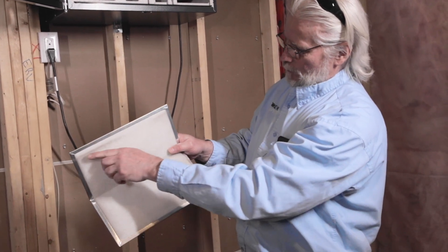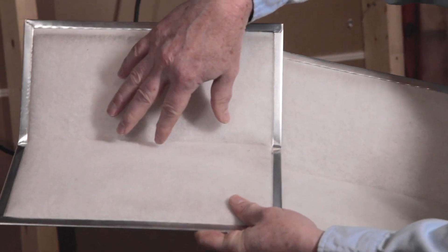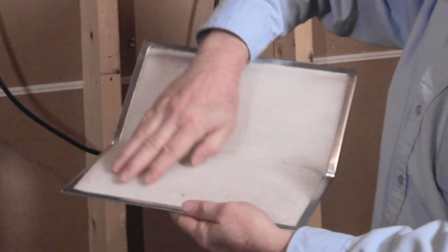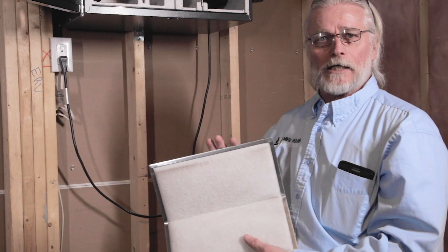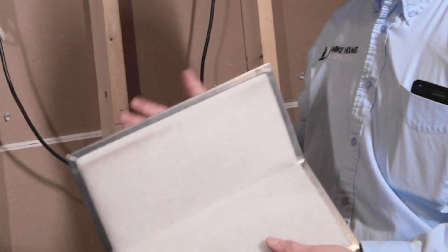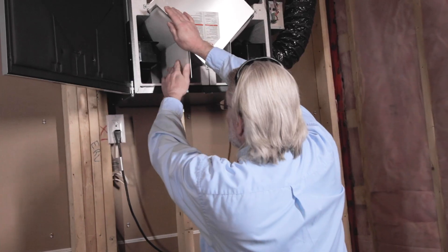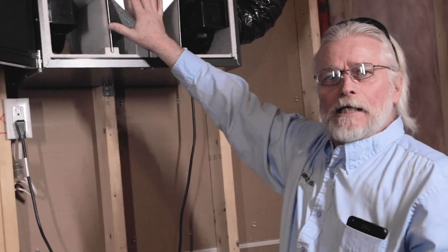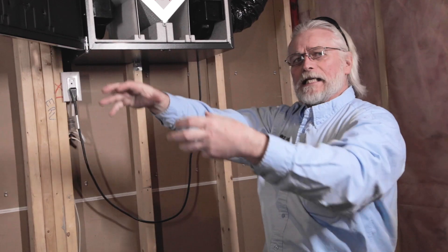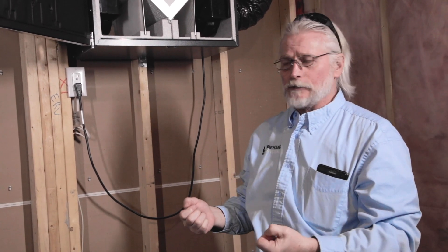As you can see, we got a little bit of dirt building up here. If you wash these things every three months, every four months, you should be fine. It's going to be seasonal as well. Obviously, we're going to get a lot more dirt and dust debris in the spring and in the summer and in the fall. The wintertime, they're probably not going to get quite as dirty, just because there's not as much debris floating around outside. This will definitely help with our indoor air quality. If this can't breathe properly, the filters get clogged, you're not getting that full supply of air exchange that is going to make our homes healthier as well.